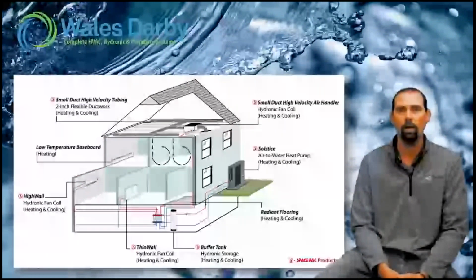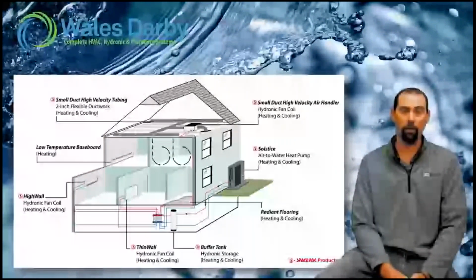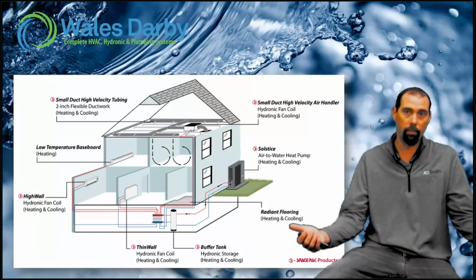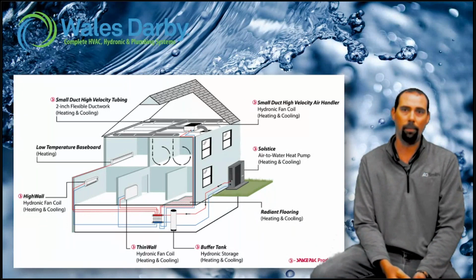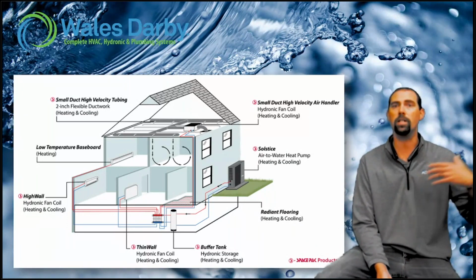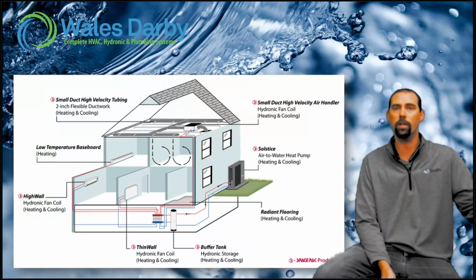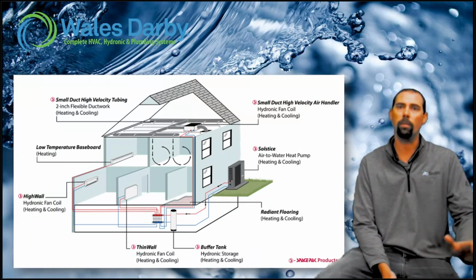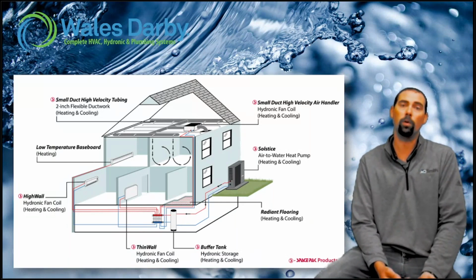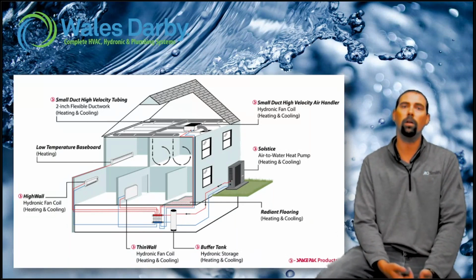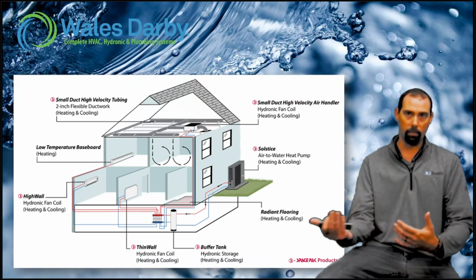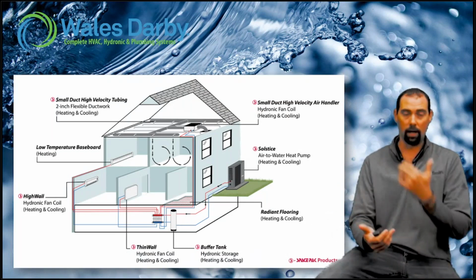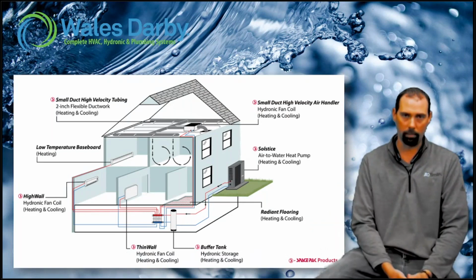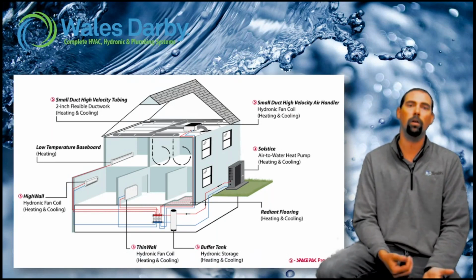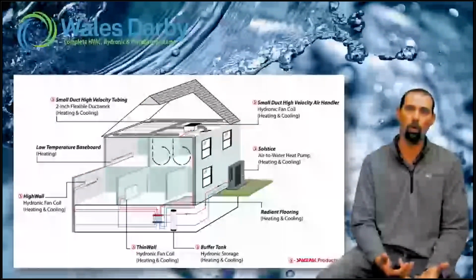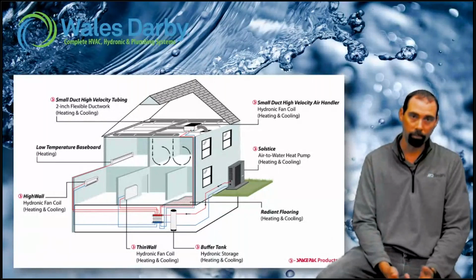That's up to you guys, and what it really comes down to is the load of the building, the envelope of the building, how many BTUs. If you paid attention last week, it's not so much about temperature, that doesn't worry me. What worries me is delivering the BTUs needed to satisfy that load calc. So before we can pick all these different components and figure out what's going to work best in your application, we need to know what the load calculation is, what do we need to accomplish here for comfort.